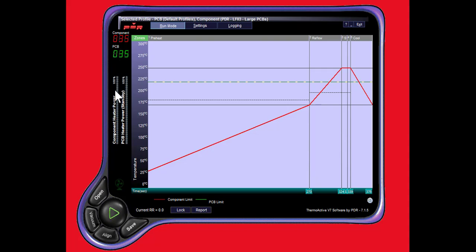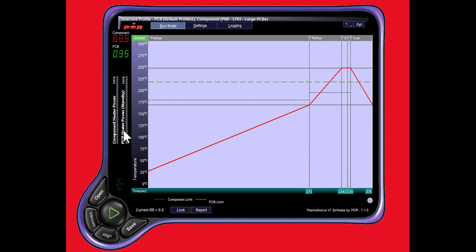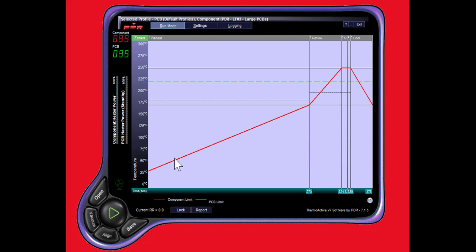Moving down the pathway on the left hand side margin right here, we see two LED indicators. One is a component heater power. The second over here on the right hand side is a PCB heater power. These two LED indicators indicate the demand on the system to develop both back heat and top heat in order to develop the ramp rate right here.